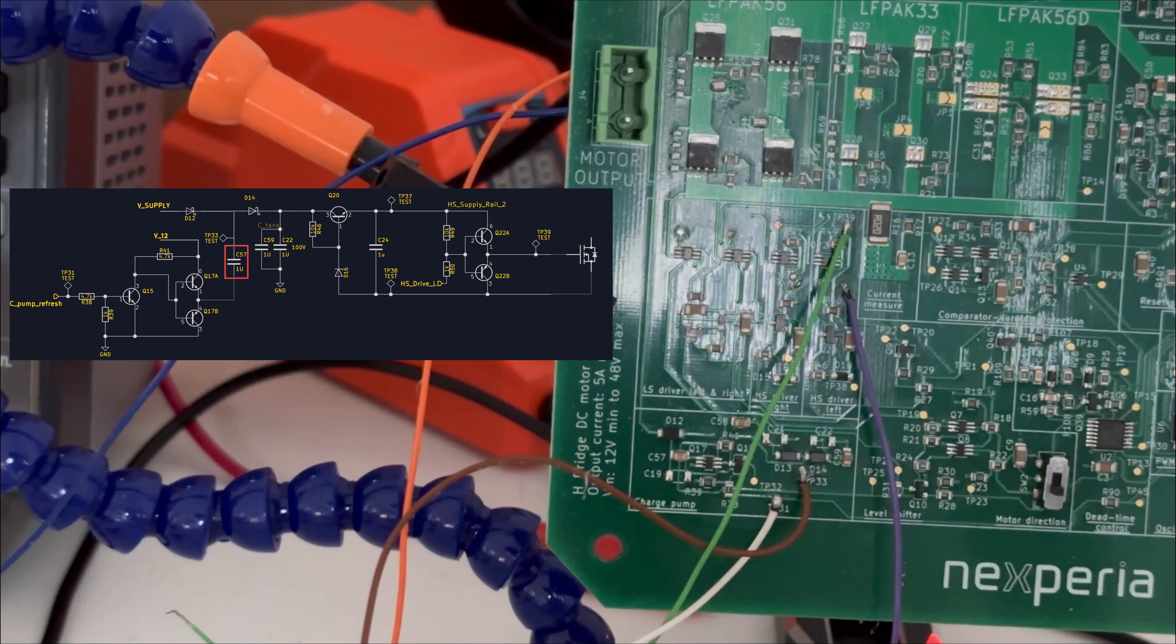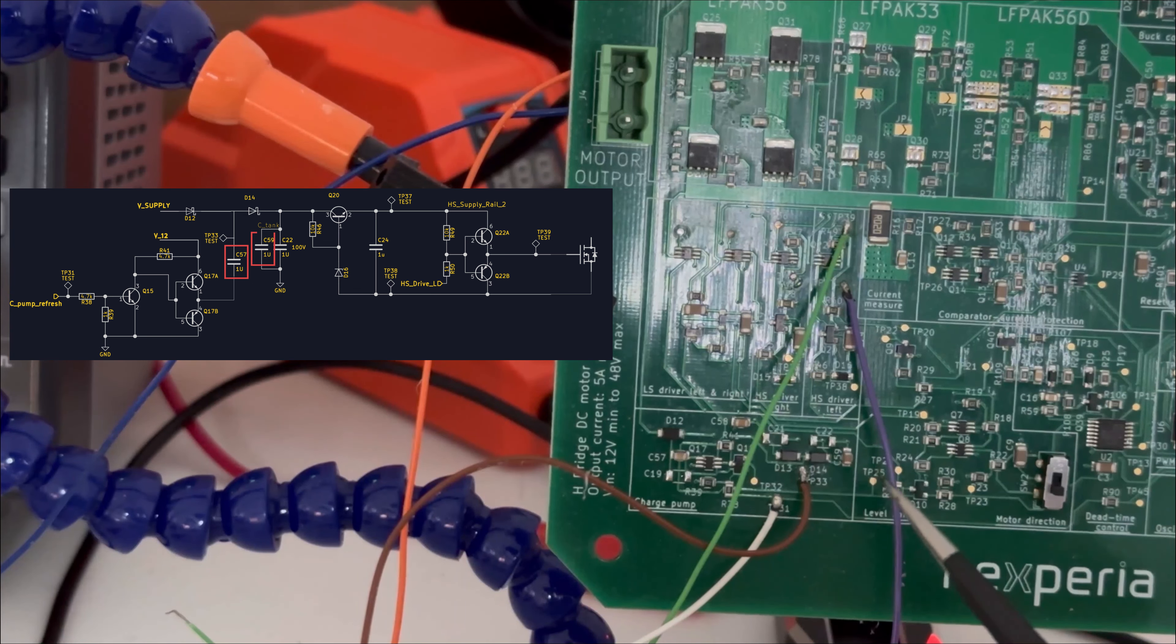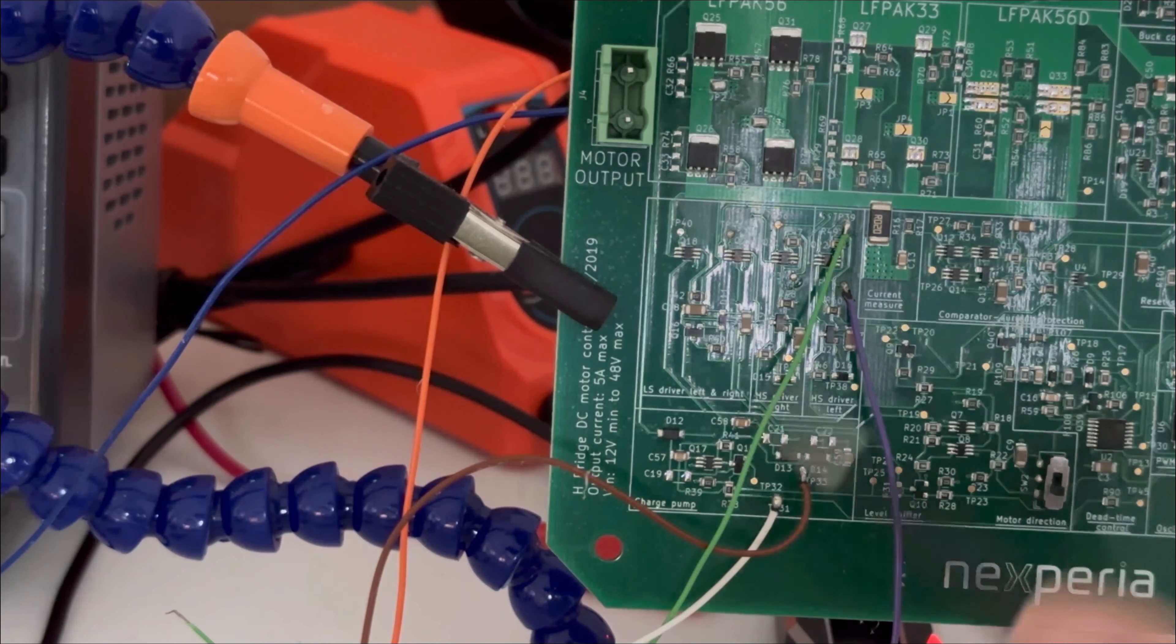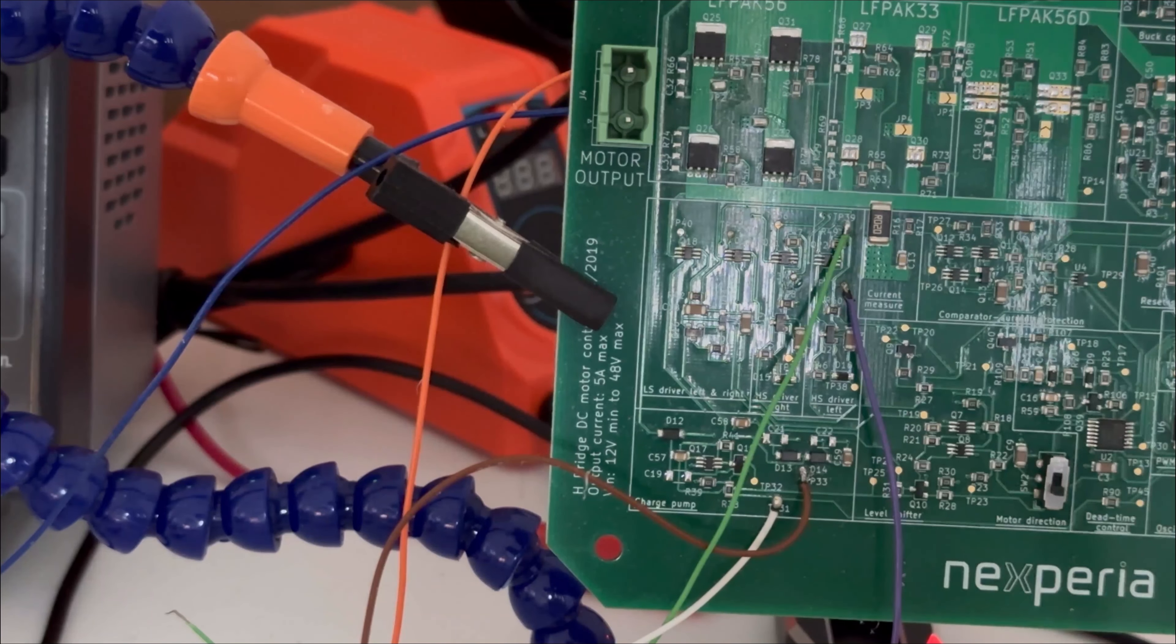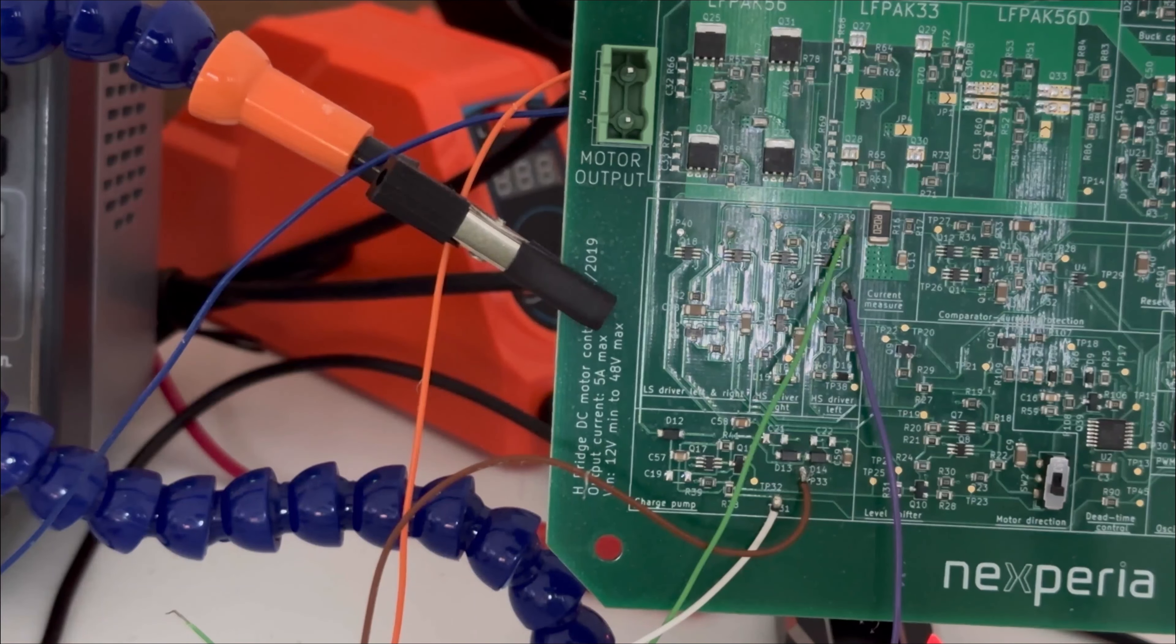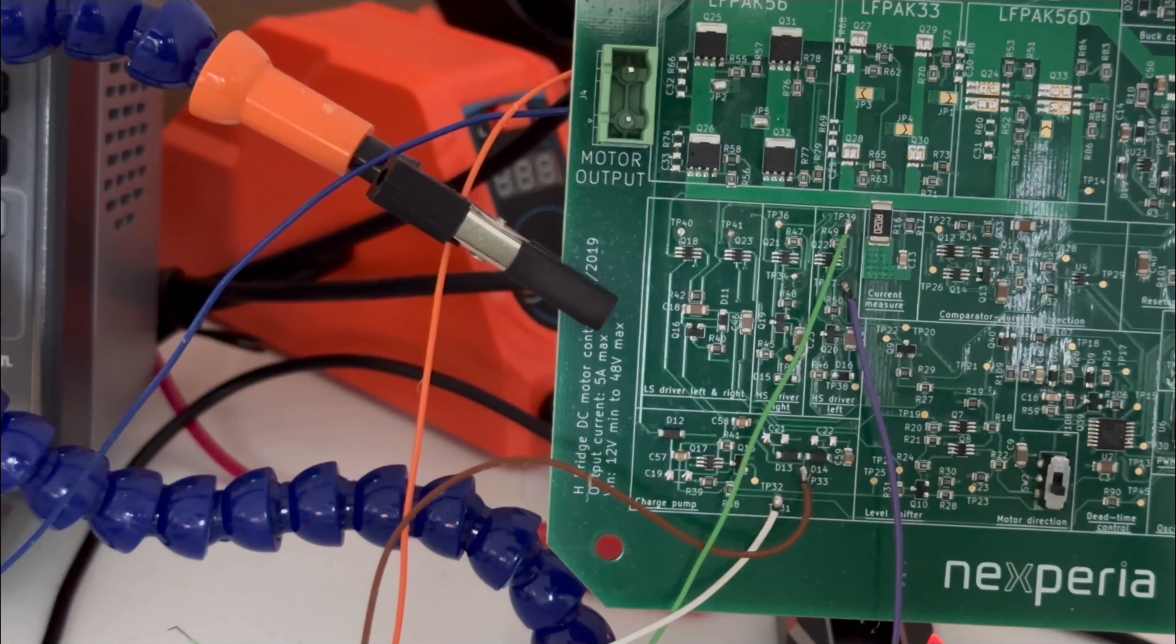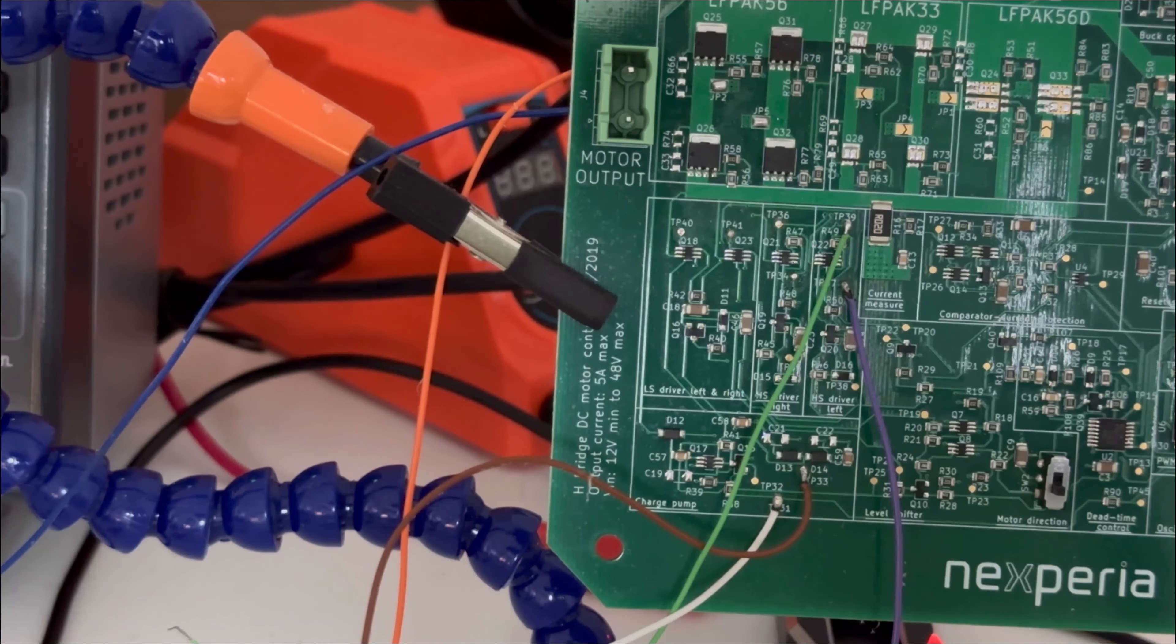This is the C57, which is the charge pump capacitor. This is the C59, which is the storage capacitor. And we have taken multiple test points out to check the waveform of the charge pump. Let's check out the clock pulse at TP39.